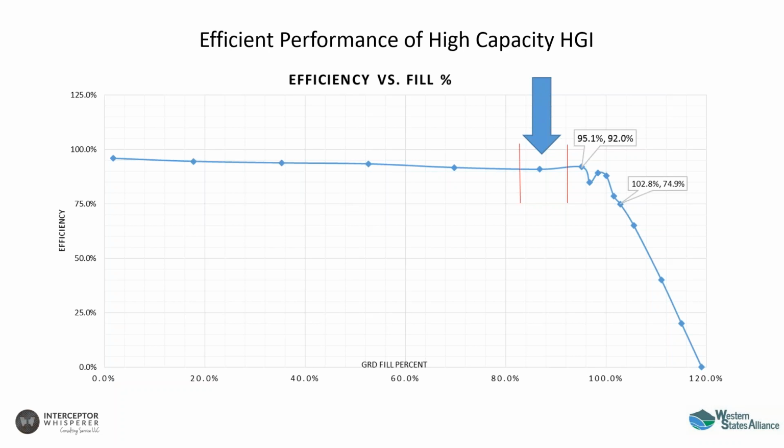Now you know where it came from. It came from legacy hydromechanicals tested to the minimum. So we don't want to apply that to the newer high capacity types because they certainly are doing much better than the minimums. We also don't have any test data from the gravity grease interceptors to know if it's accurate.